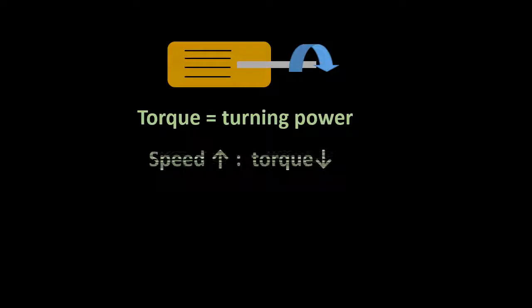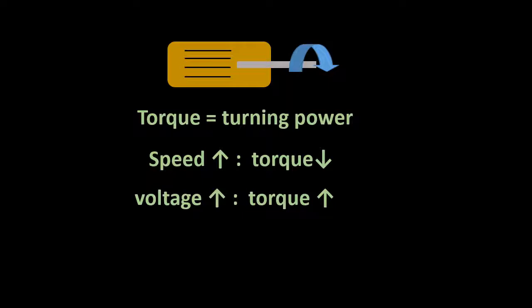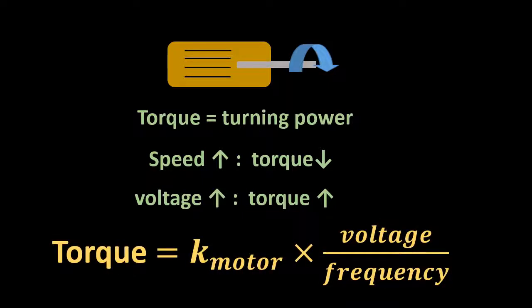A motor's torque is its rotational power. Motor torque will decrease with increasing speed, and increase with increasing voltage. Stated as an equation, we have torque equals K times voltage over frequency, where K is a constant for that particular motor.